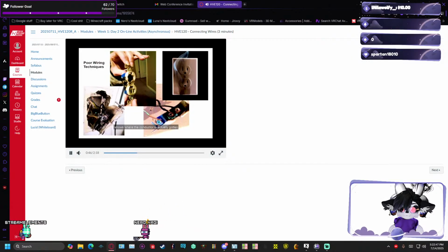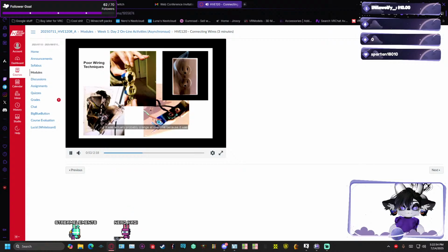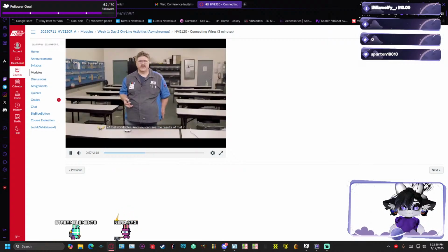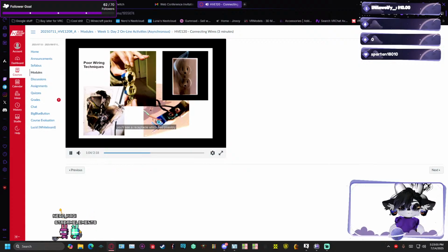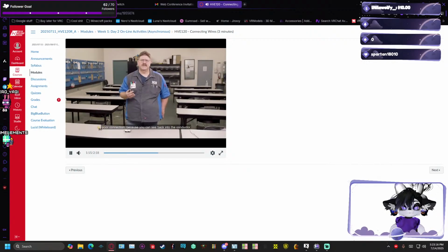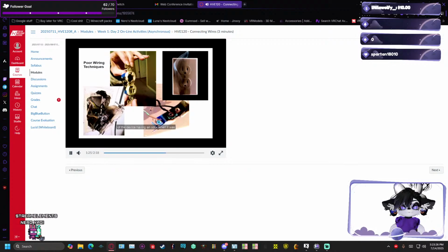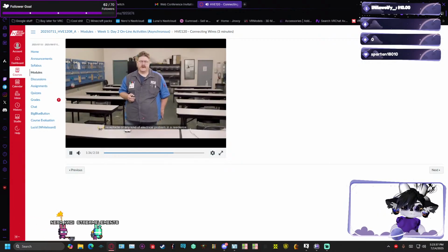The one on the left on the bottom shows where the conductor has actually gotten so hot that it's turned white. It was actually probably orange at one time because it was a resistive connection, and that burned the oils off of that conductor, and you can see the results of that in that picture there. On the bottom right, you'll see a receptacle which had possibly moisture in it. If you see on the copper, you see green, and the only thing that turns copper green is moisture. So something got into that, on top of the fact that it had a poor connection, because you can see back into the conductor where the insulator is blistered and actually separated from the conductor. It got that hot. On top of it, if you remember, I talked about the safety of the device having an odor when it was failing or burning. And that picture shows the smoke coming from it. That is one of our best tools for locating the problem with a receptacle or any kind of electrical problem in a residence.